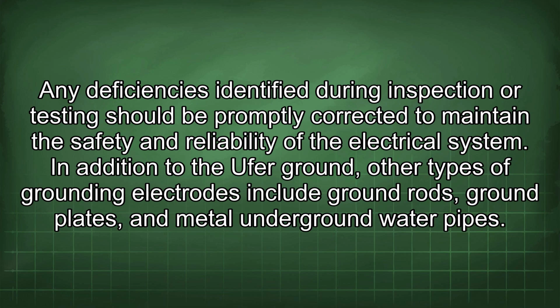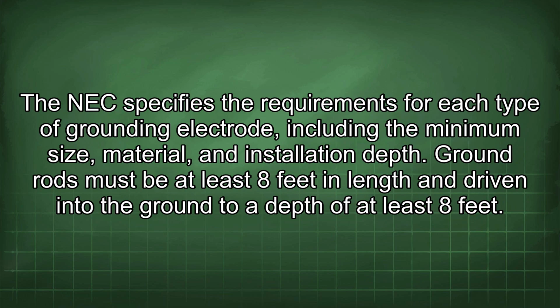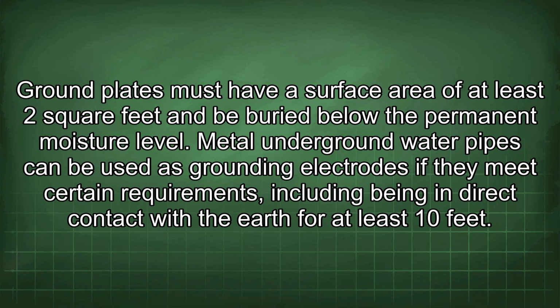In addition to the Ufer ground, other types of grounding electrodes include ground rods, ground plates, and metal underground water pipes. The NEC specifies the requirements for each type of grounding electrode, including the minimum size, material, and installation depth. Ground rods must be at least 8 feet in length and driven into the ground to a depth of at least 8 feet. Ground plates must have a surface area of at least 2 square feet and be buried below the permanent moisture level.